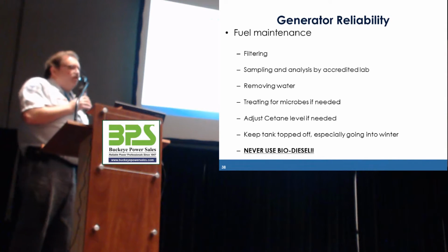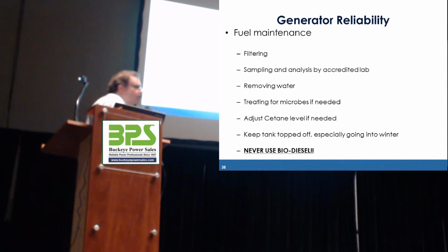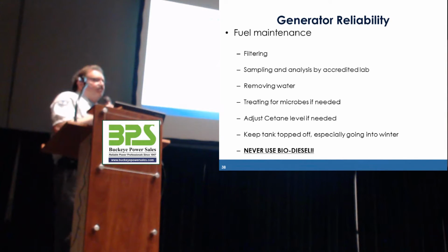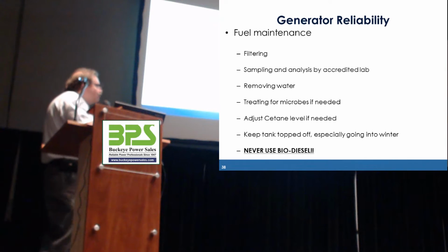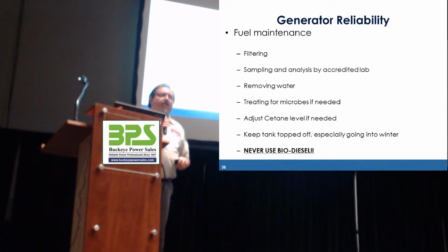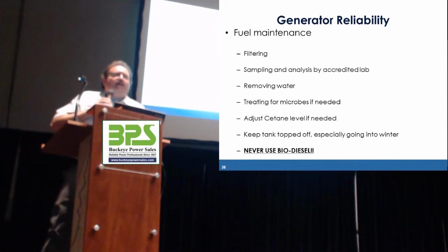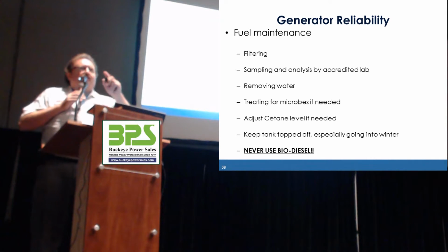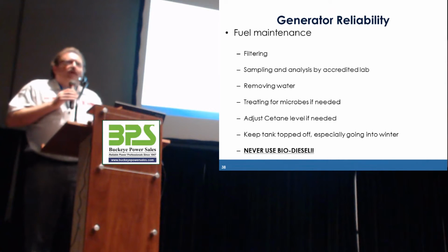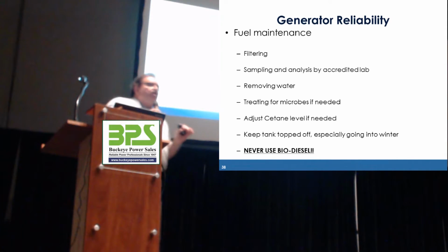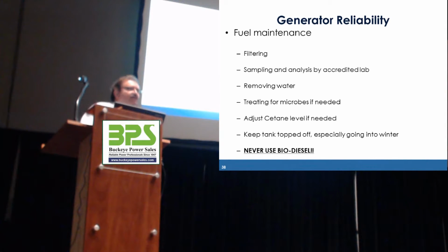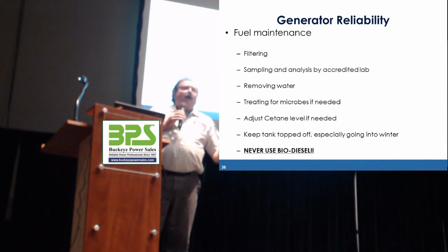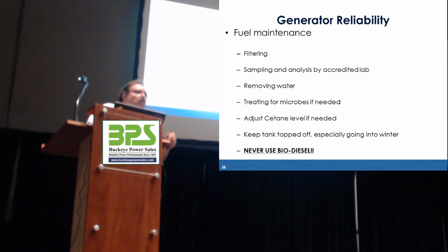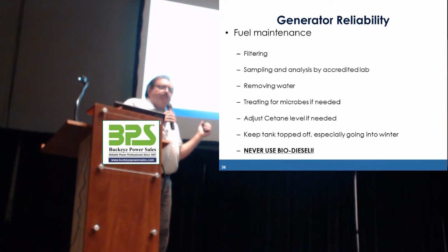And I know this in NFPA 110 is a should, but all the manufacturers will tell you it's a shall. Never use biodiesel in an emergency generator. Biodiesel is fine if you're going to put it in your tractor or your truck and you're going to burn it within the next 30 days. But when it sits, it does such a good job of cleaning the fuel system inside the engine that it just cleans everything out of the fuel system and trashes the fuel system. Most engine manufacturers will not warranty a fuel system damaged engine if it's got biodiesel in it.